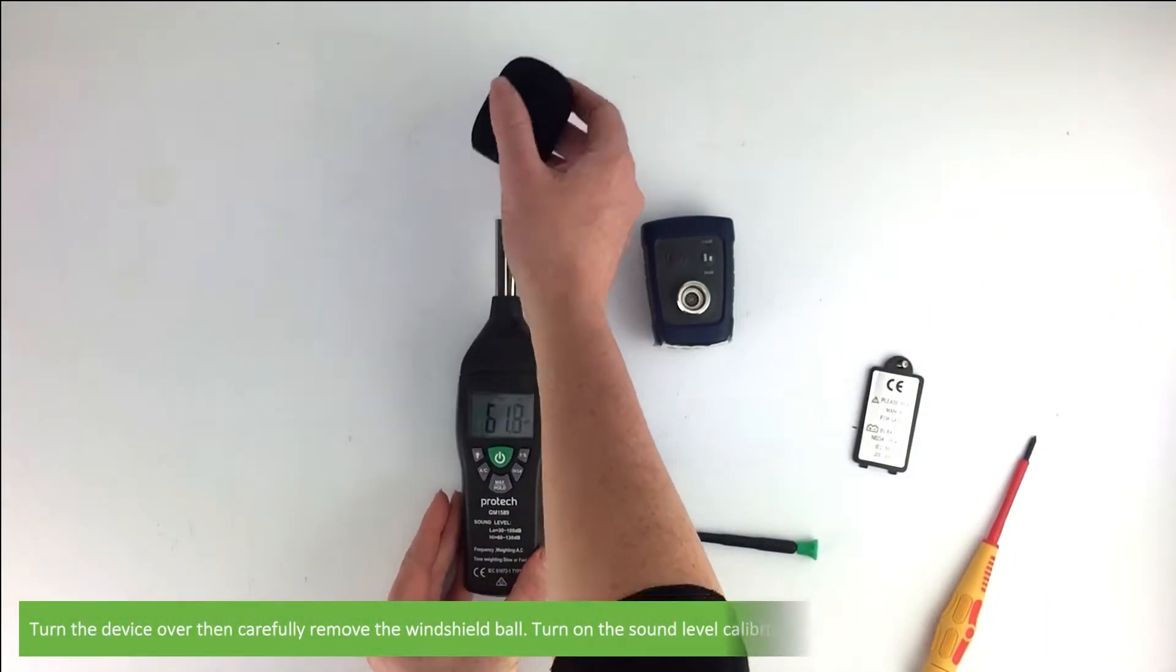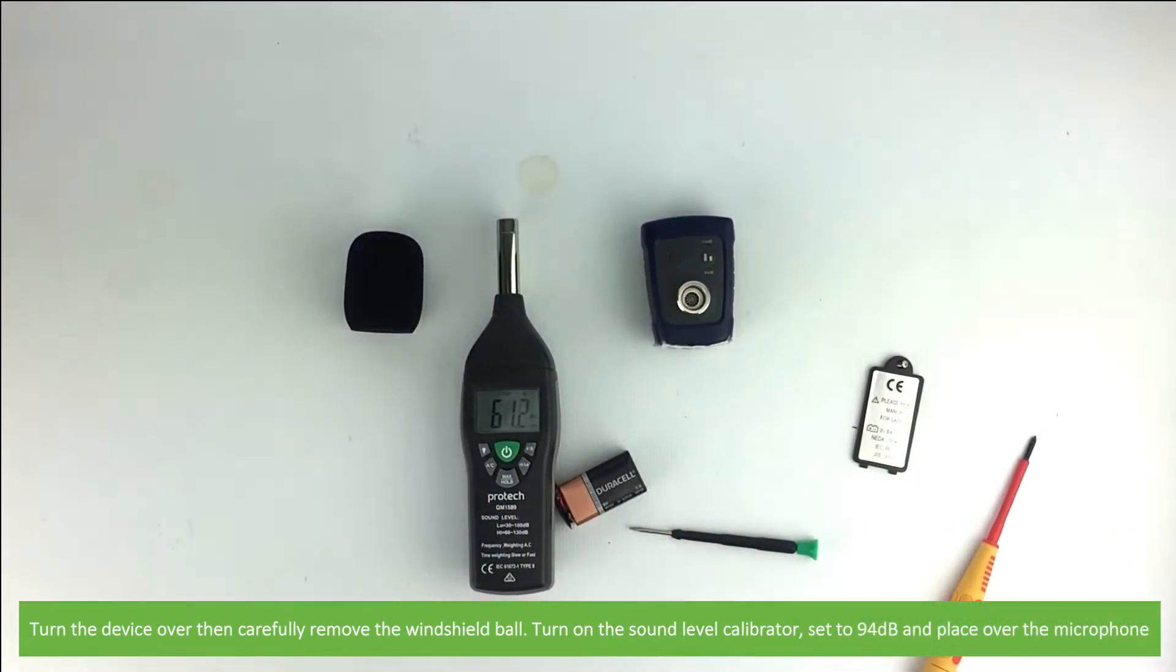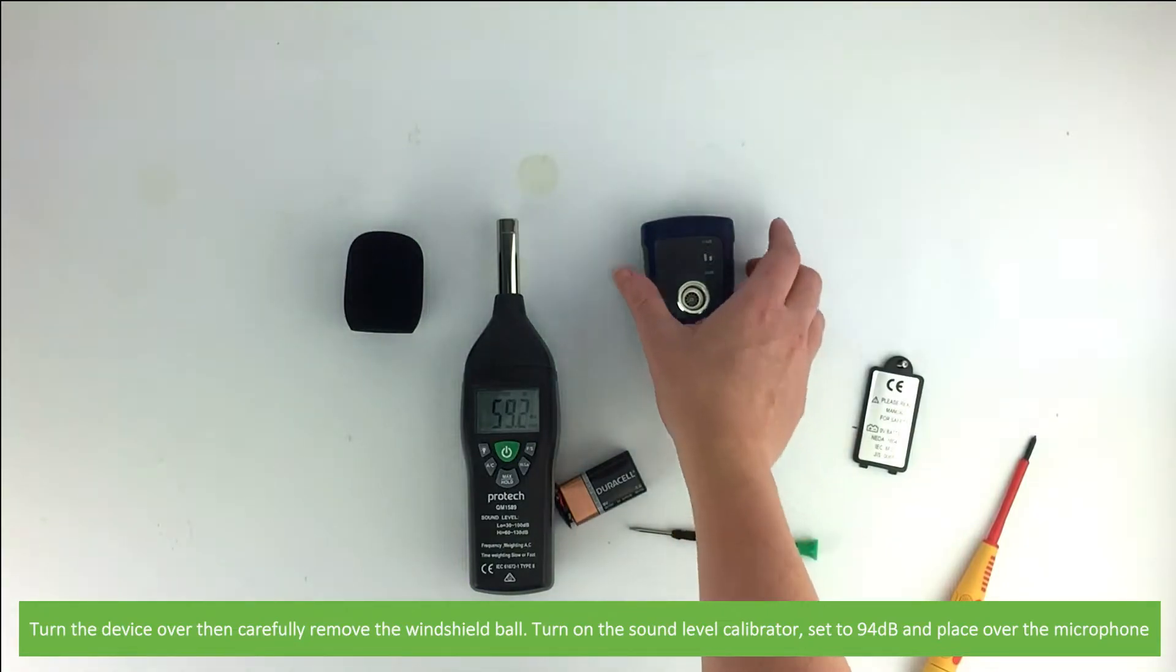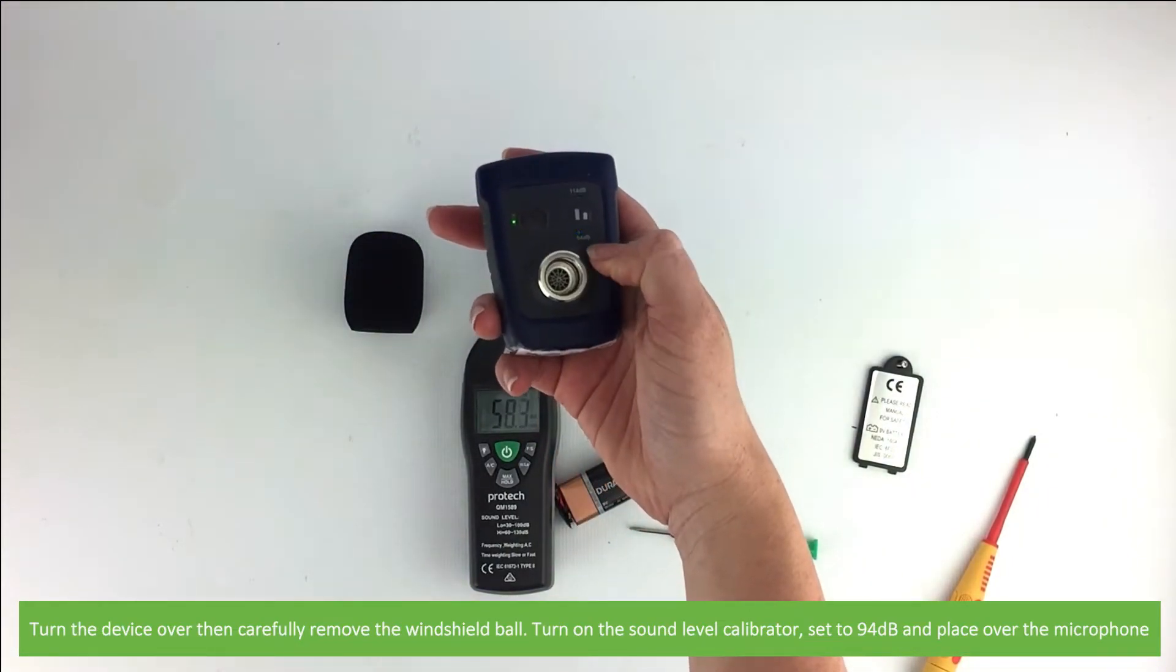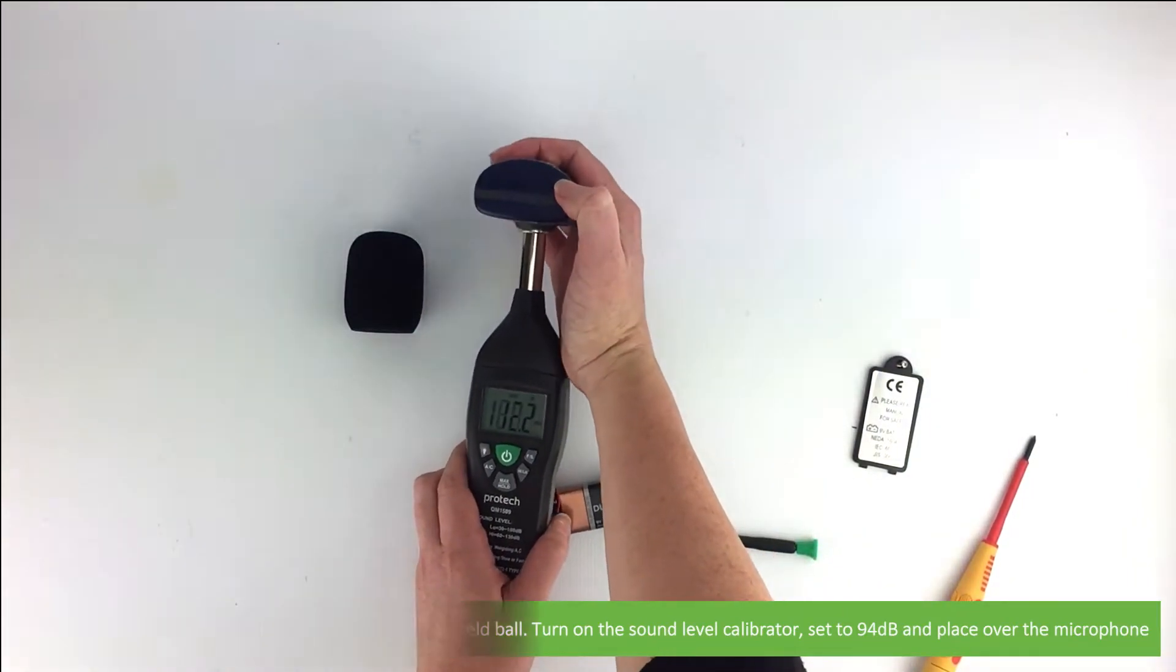Turn the device over and carefully remove the windshield ball. Turn on the sound level calibrator and set to 94 decibels. Then place over the microphone.